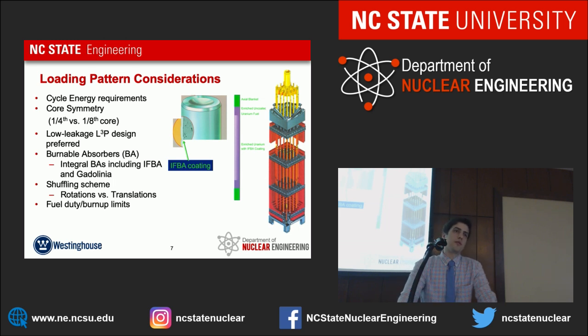The burnable absorbers we're using are IFBA, integrated fuel burnable absorber, as well as gadolinium. The IFBA is coated on the outside, and it'll burn up after about 5,000 megawatt days per MTU, but the gadolinium is distributed throughout the actual fuel, so it will last a little longer through the core cycle. And the gadolinium actually will displace fuel, but the IFBA will not, so there are pros and cons with both.